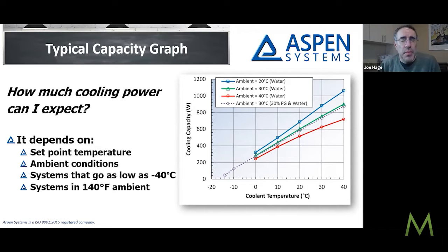I'm just curious because that's pretty unsurvivably hot. Is there anything on the market that goes higher than 140? There are limits to the vapor dome with the refrigerants, so the maximum we could go to is about 71 C. We have done systems in that environment—let me convert that, it's in the neighborhood of 165 F. At that point, literally you can't get liquid out of the refrigerant, so that's where the hard stop is on the upper ambient temperature.